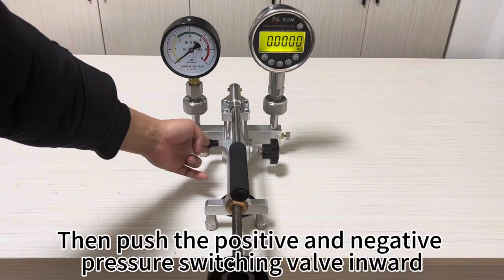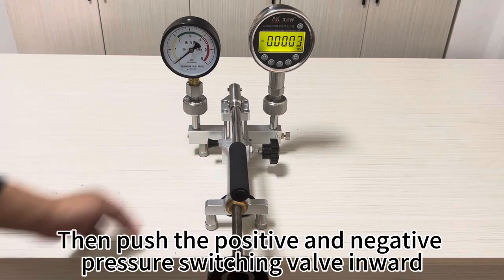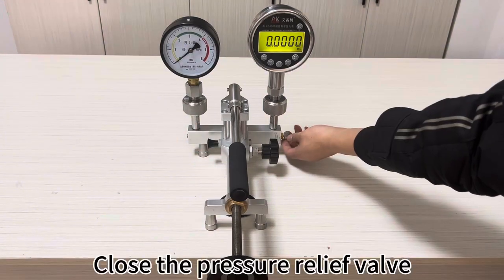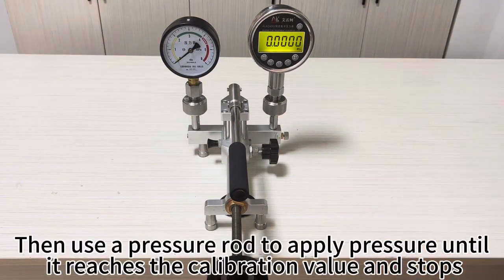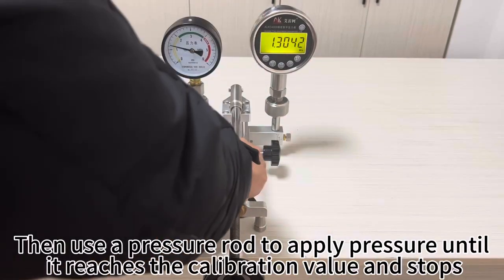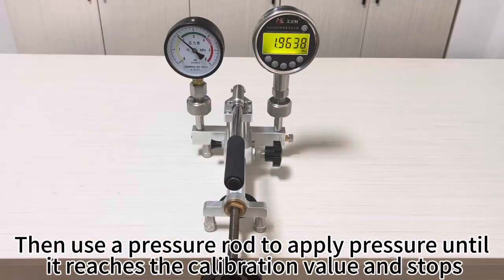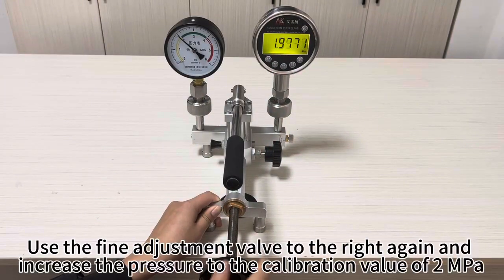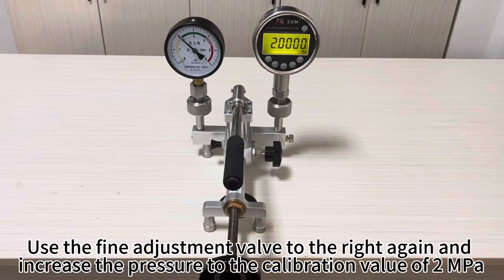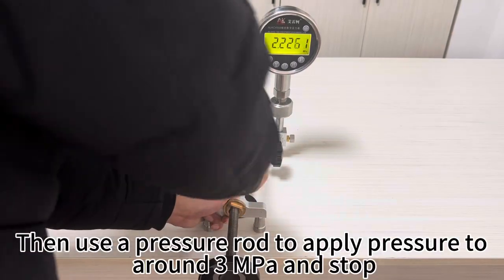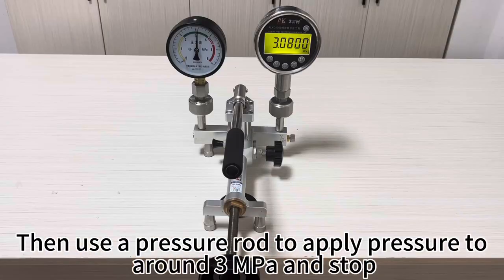Then push the positive and negative pressure switching valve inward. Close the pressure relief valve. Then use the pressure rod to apply pressure until it reaches the calibration value and stops. Use the fine adjustment valve to the right and increase the pressure to the calibration value of 2 MPa. Then use the pressure rod to apply pressure to around 3 MPa and stop.